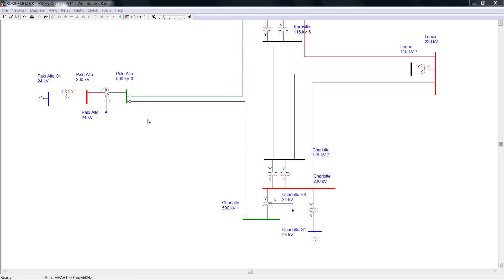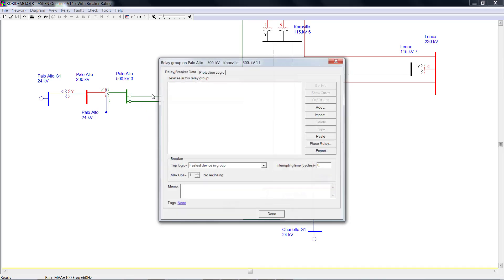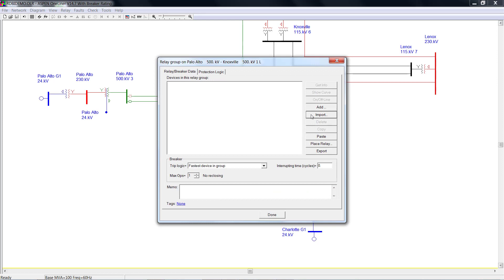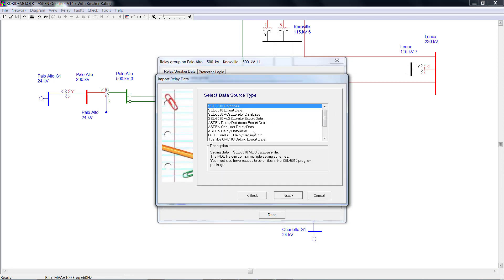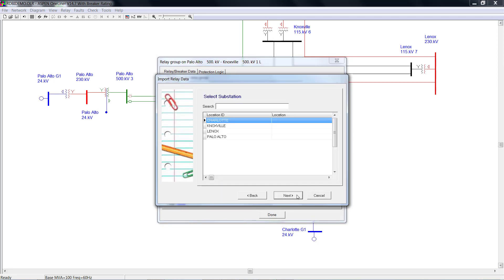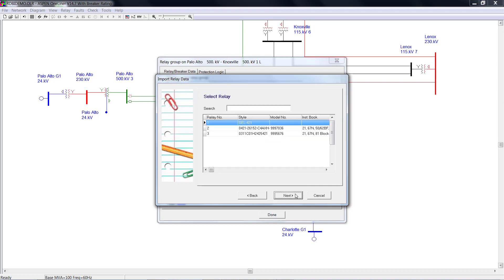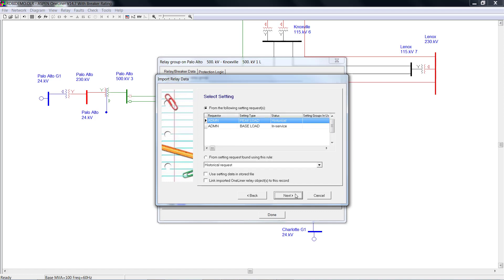You could import the relay setting either from a relay group or from an existing relay. If we import from a relay group, double-click the relay group, click Import, select Aspen Relay Database, and click Next. Select the substation, select Relay, and select Setting.